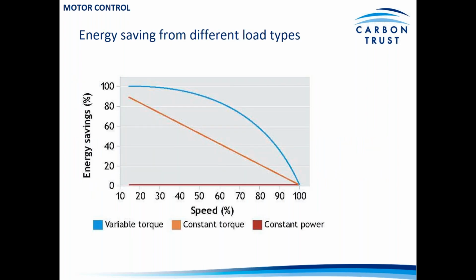And indeed, as mentioned earlier, the speed power relationship is different for different types of load. So essentially, where you have a constant power, there won't be an energy saving to be had in that case. That's the red line along the bottom there. Where you have a constant torque arrangement, essentially the saving will be proportional to the change in speed. But where the change in speed really comes into its own is on the application to variable torque loads. And you can see here the nature of the graph means that even small reductions in speed lead to large energy savings.